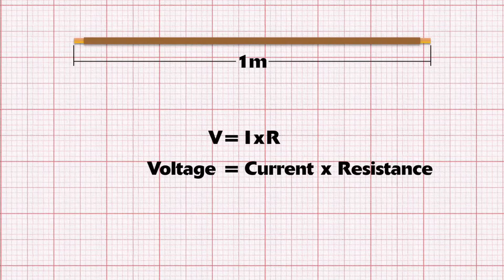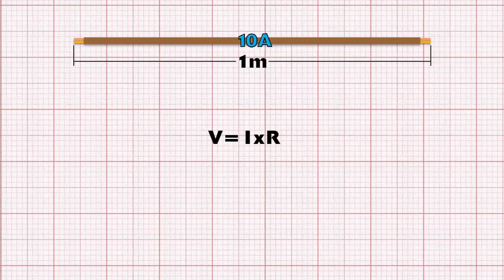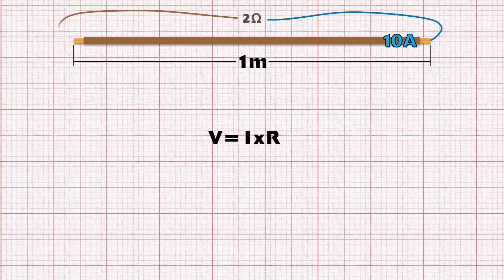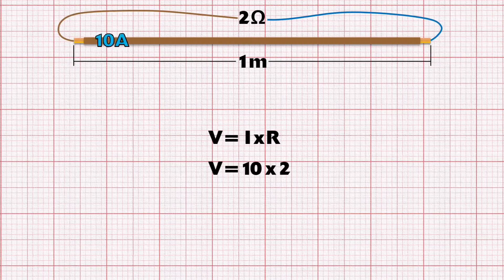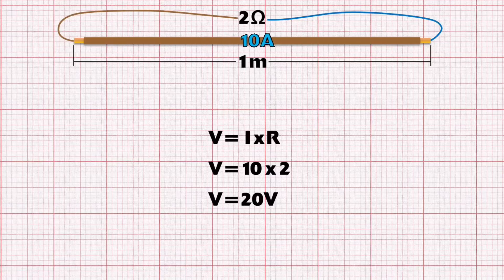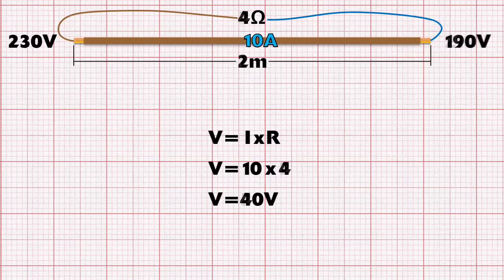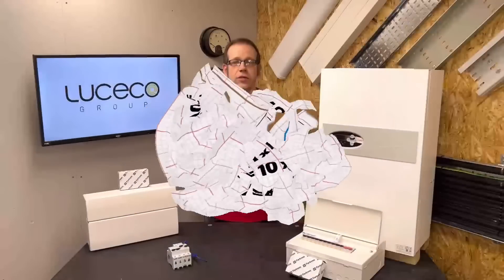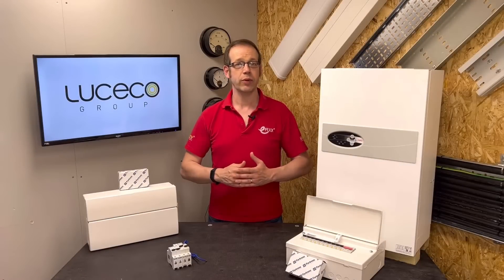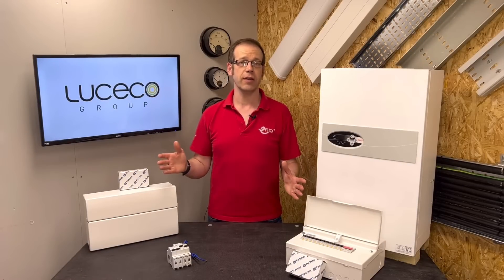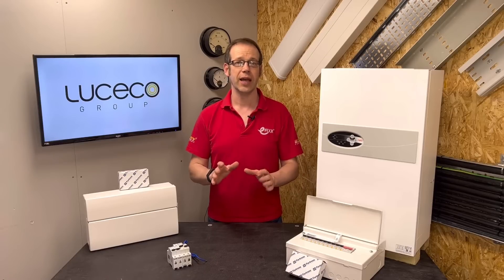Using some exaggerated numbers to illustrate the point: if we've got 10 amps running through a conductor with a resistance of 2 ohms, plugging those numbers into our calculation gives us V = 10A × 2Ω = 20 volts. So to push our 10 amps of current through this conductor, there has to be a difference of 20 volts between one end and the other. If we double the length of our conductor, we'll lose 40 volts between the start and end point. For every metre we add in length to the supply conductor, we lose 20 volts from the supply voltage. If we've got a long circuit, the voltage at the end simply can't push the current through the load and it won't operate as it should.